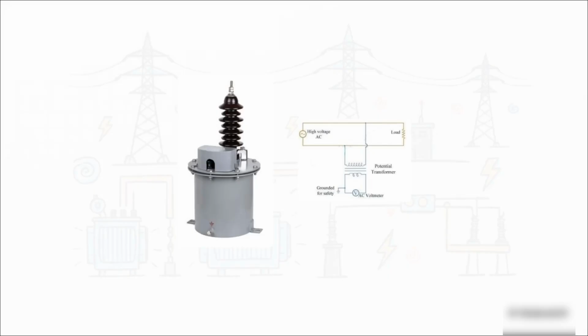Now, for those circuit breakers to know exactly when to trip, they have to continuously measure the electricity. But how in the world do you plug a regular meter into a 400,000 volt line? Well, you don't. That would be a disaster. Instead, we use instrument transformers, specifically potential transformers to measure voltage and current transformers for current. They step these deadly, massive values down to incredibly safe, manageable levels. A potential transformer might step 400 kV down to just 110 volts, and a current transformer might step 2,000 amps down to just 1 or 5 amps. This clever trick allows standard, everyday relays and meters to safely monitor the grid's health in real time.